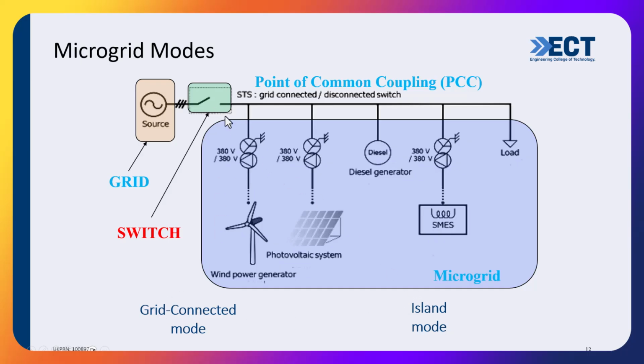In grid-connected mode, once you close the switch, your bus is dictated and dominated by the grid—the voltage and frequency here are fixed by the grid, and all the resources interact with it by supplying more or less power depending on the frequency and voltage. But in island mode, that's controlled instead by, for example, a diesel generator or one of the battery storage systems.